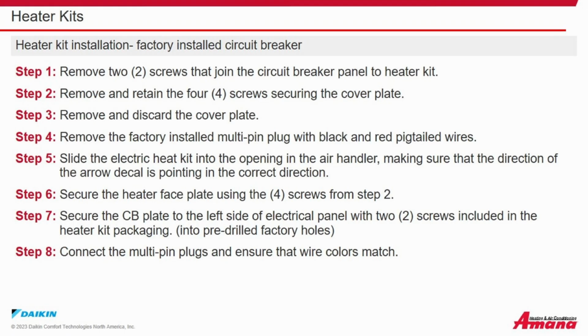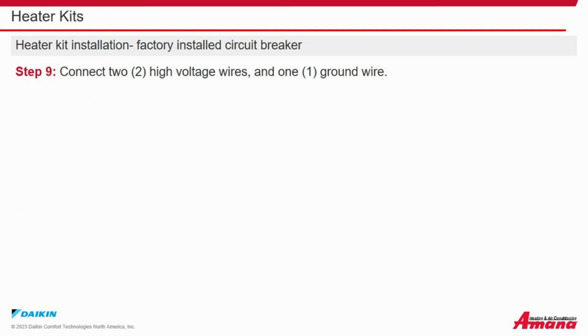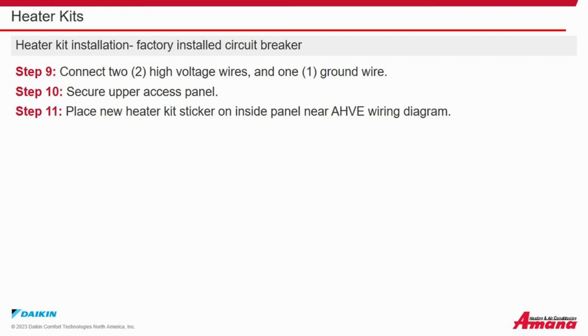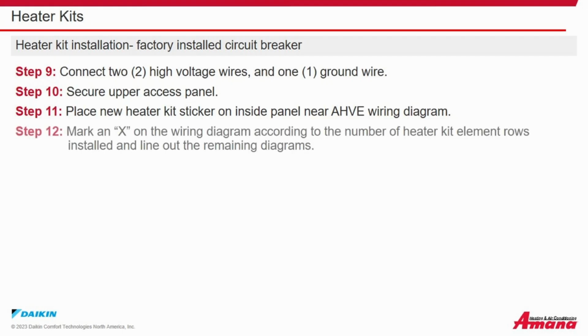Step 8. Connect the multi-pin plug and ensure that the wire colors match. Step 9. Connect the 2 high-voltage wires and 1 ground wire. Step 10. Secure the upper access panel. Step 11. Place the new heater kit sticker on the inside panel near the AHVE wiring diagram. Step 12. Mark an X on the wiring diagram according to the number of heater kit element rows installed and line out the remaining diagrams.